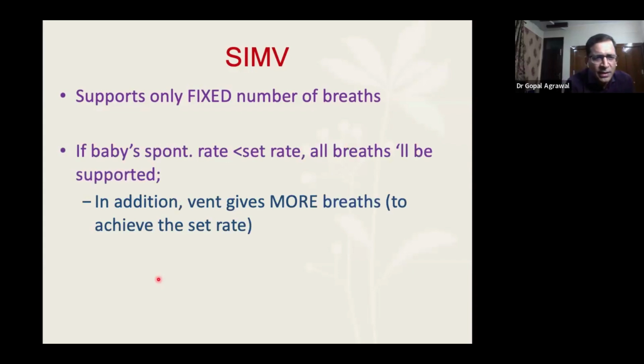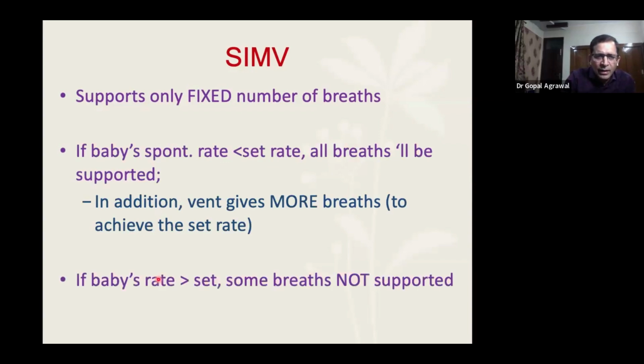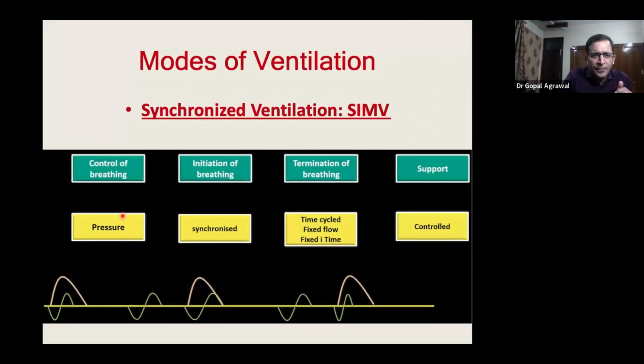For example, if the baby's spontaneous rate is less than the set rate, suppose the baby's spontaneous rate is 20 and the set rate is 30, all breaths will be supported and the ventilator will give 10 extra breaths to achieve the set rate. If the baby's rate is more than the set rate, suppose the baby is breathing at 40 and the machine's rate is 30, 10 breaths will not be supported and 30 breaths will be synchronized with the baby. So it is one step better than IMV, where the fixed number of breaths will be supported. Control of breathing in SIMV is pressure controlled. Initiation of breathing is by the baby and it will be synchronized with the baby. That's a better advantage than IMV.